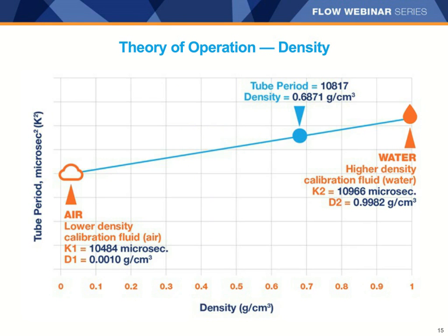Density calibration is performed at the factory on air and water. Meters are filled with air, resulting in a tube period, or K1, of 10,484 microseconds in this example. Next, the meter is filled with water, which results in a tube period, or K2, of 10,966 microseconds. Those two values, K1 and K2, are plotted against the density of the two fluids the meter is calibrated on, air and water. In this case, D1 is the density of air, and D2 is the density of water.